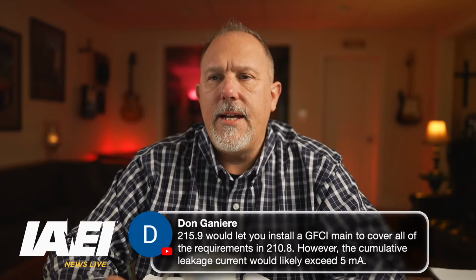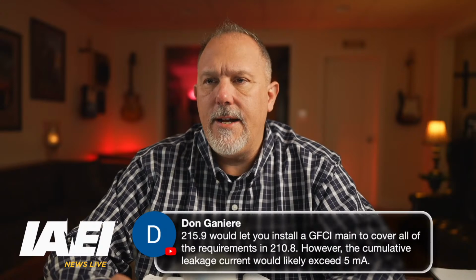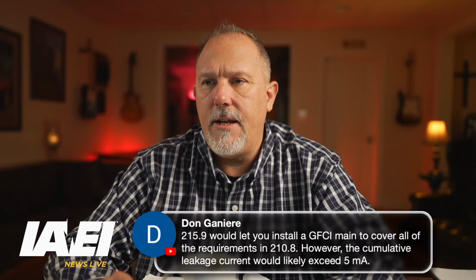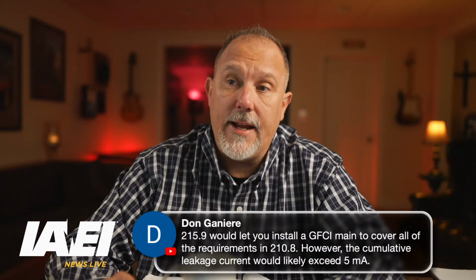But in any case, you go upstream and you can provide that GFCI protection, and it can replace that requirement. Hey, Lou Petrucci, thank you for joining in. Really appreciate your joining in and helping out with the dialogue here. Well, Don Ganiere says 215.9 would let you install a GFCI main to cover all of the requirements of 210.8.